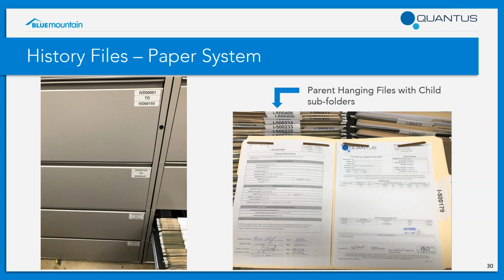So we have a filing cabinet, and each drawer in the filing cabinet is going to denote the range of ID numbers that are in that drawer. Once you open the drawer, there's a bunch of hanging folders with the parent ID on the file. And then within that file, there are subfolders with your instruments that are related to that parent. And then in the individual folders, as you open them up, we'll have the master equipment record on the left-hand side and the calibration certificate or preventive maintenance certificate on the right-hand side with the most recent on top.